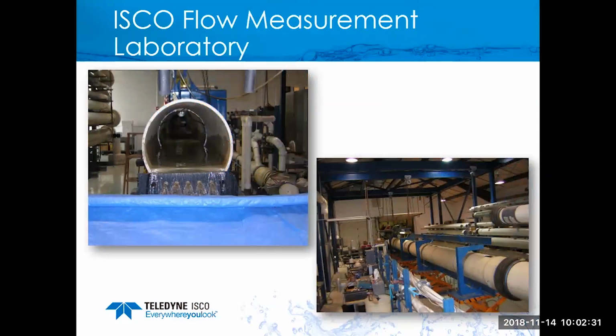This is the ISCO Flow Measurement Lab. Some of you have been to the facility and have seen this, but if you haven't, this is one of the really nice features behind the facility here. We can use 4-inch up to 24-inch pipes. Flow ranges up to 2,800 gallons per minute. We've developed all of our area velocity technology on this facility, and this has been very, very useful. It helps us simulate a lot of different hydraulic conditions, as well as what happens if I dam up the flow, what happens if this happens. So we are able to really do a lot with design work, but we also use it a lot for future enhancements and improving performance of all our technologies.